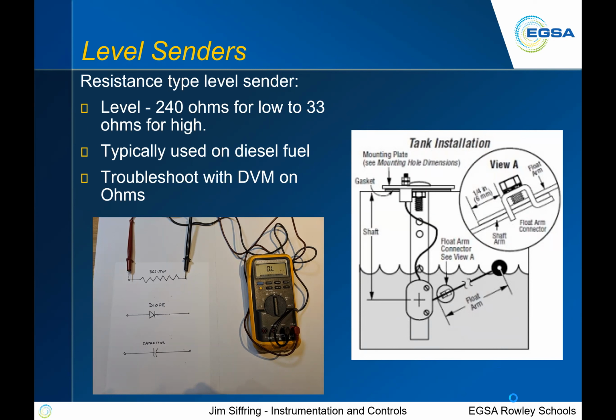And again, troubleshooting with this type of device is very simple. The resistance across that device should change with the sweep of that arm. More commonly, it'll read something completely out in the weeds, like really high resistance, or it might read 0 resistance for a short, or might be completely open.